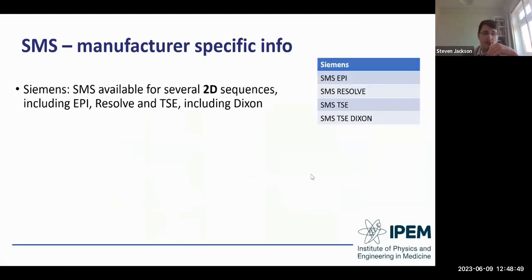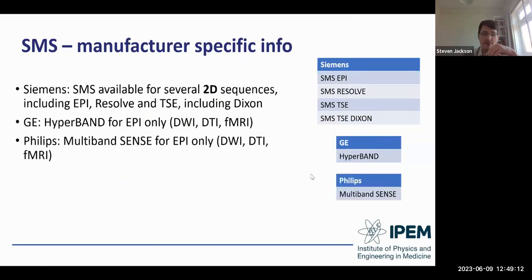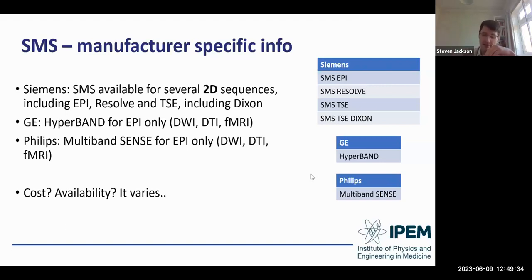For SMS manufacturer-specific information: on Siemens it's available for several 2D sequences including EPI, RESOLVE, and Turbo Spin Echo including Dixon. On GE it's available for EPI only, usable for diffusion-weighted imaging, diffusion-tensor imaging, and fMRI. Philips' Multiband Sense technique is currently available for EPI only with the same applications. Some of these are 3T only. Cost and availability vary for each technique, and the return on investment in terms of image quality and patient throughput will differ between manufacturers.